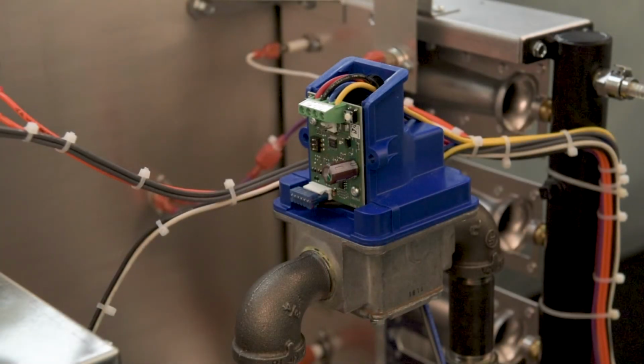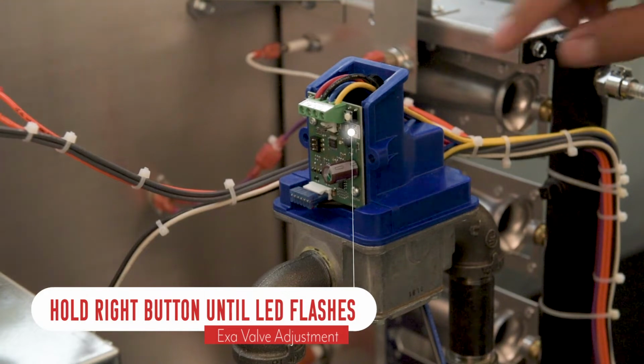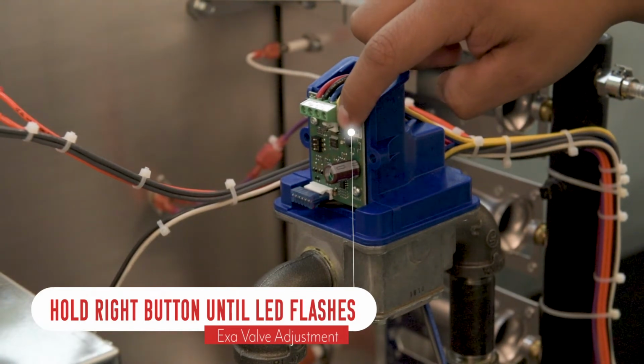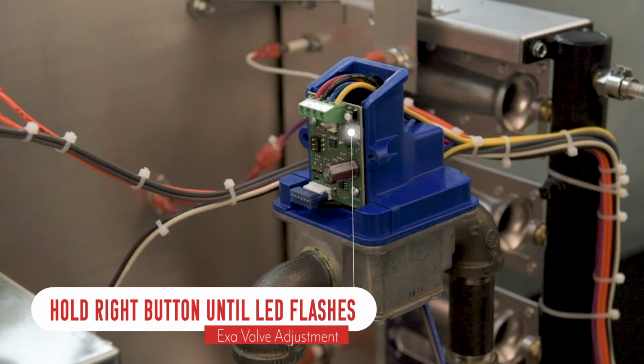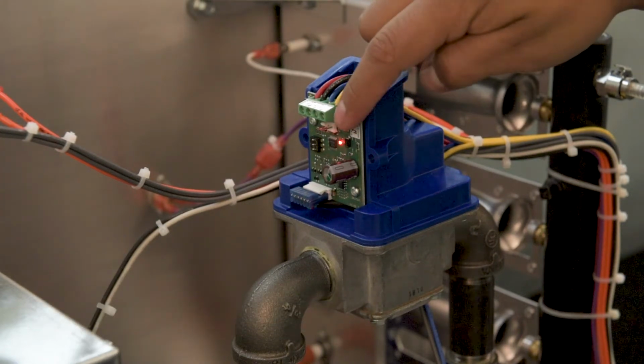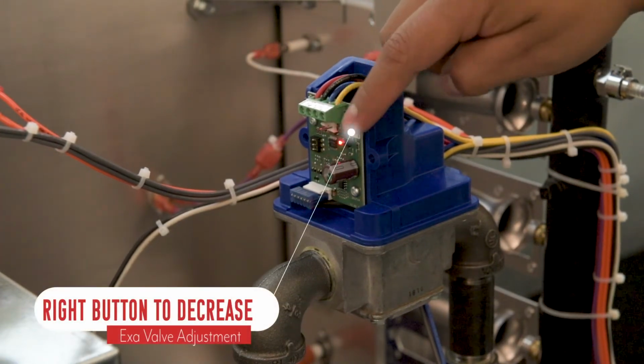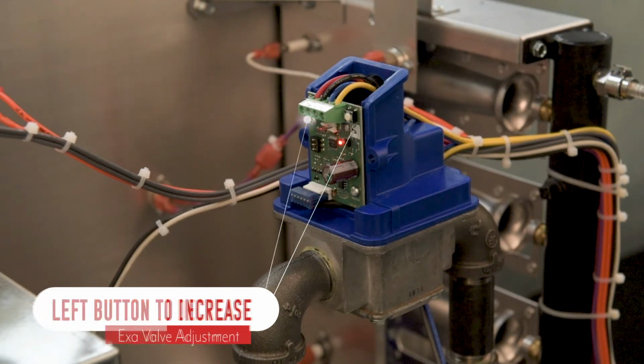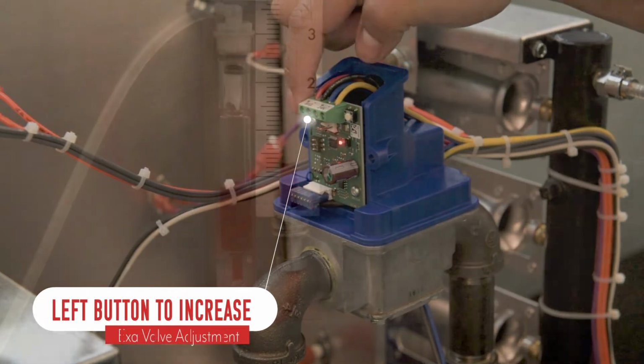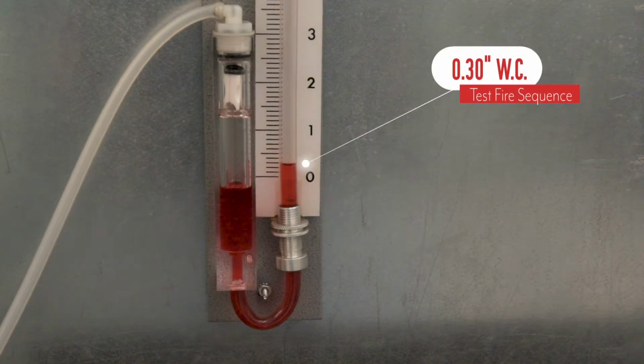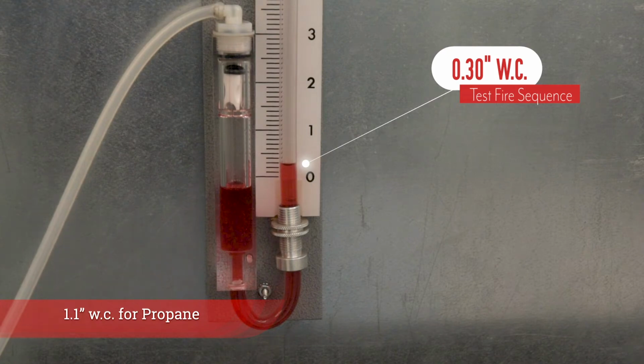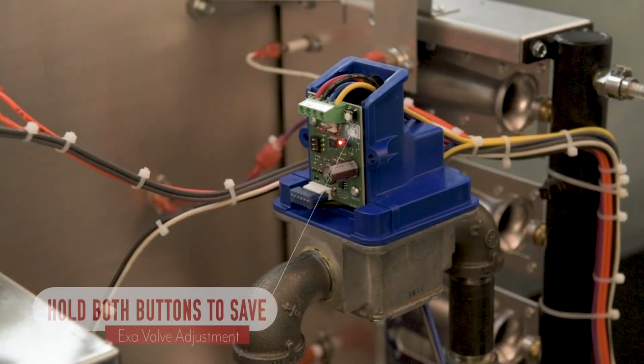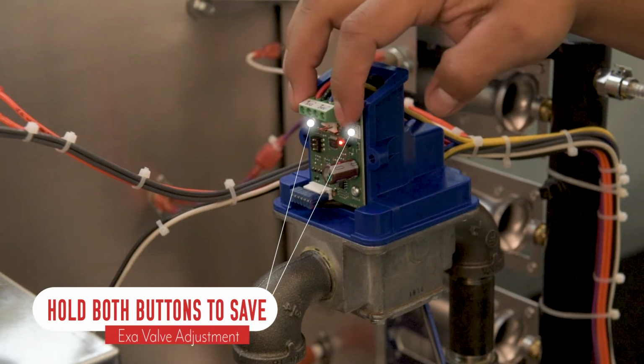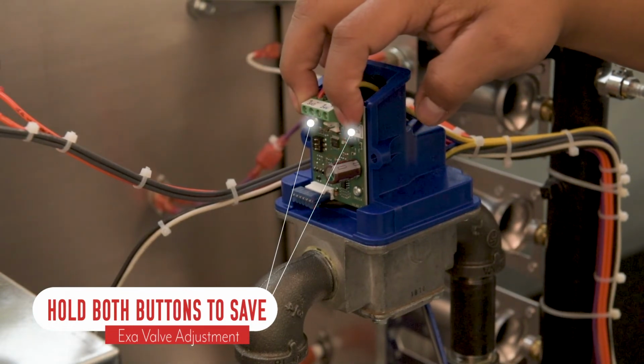If the manifold pressure is incorrect, adjust the EXA modulating gas valve by pressing and holding down the right button. A red blinking LED will flash when the valve is ready to set the low fire position. Using the right button to decrease manifold pressure and the left button to increase manifold pressure, set the manifold pressure to 0.3 inches water column for natural gas or 1.1 inches water column for propane. Once the desired manifold pressure is achieved, press and hold both buttons until the red LED turns off. This will save the low fire valve position.